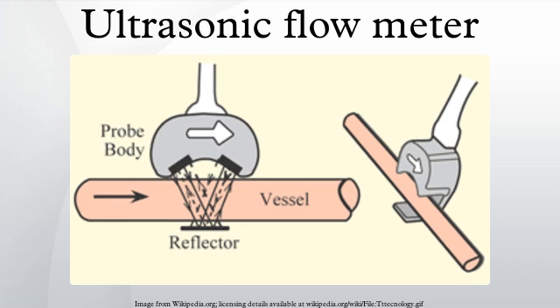Using ultrasonic transducers, the flow meter can measure the average velocity along the path of an emitted beam of ultrasound by averaging the difference in measured transit time between the pulses of ultrasound propagating into and against the direction of the flow, or by measuring the frequency shift from the Doppler effect.